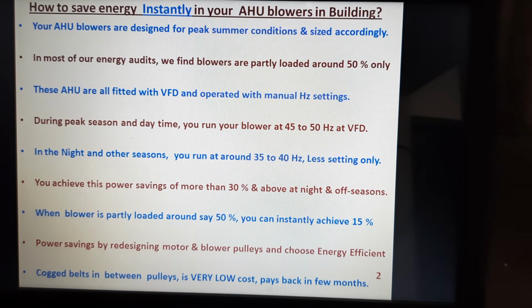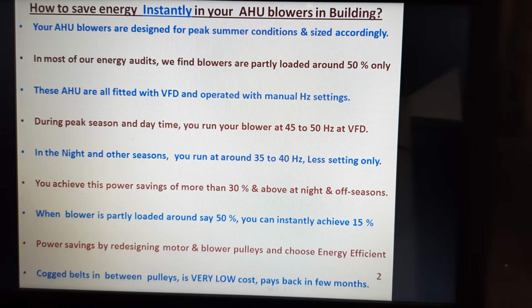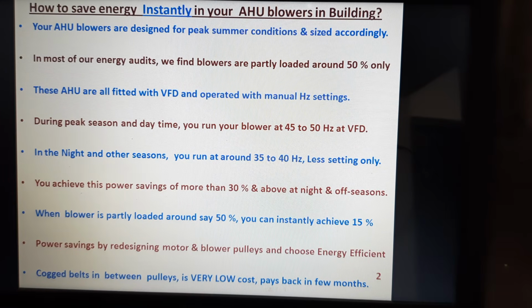Your AHU blowers are basically designed for peak summer conditions and sized accordingly. In most of the energy audits we have conducted in buildings and industries, we find the blowers are partly loaded, around 50% only, especially the air handling blowers. These AHUs are fitted with VFD and operated with manual hertz settings in some of the IT and commercial buildings, and many of the IT buildings have already switched over to BMS. They have incorporated all the HVAC systems in the BMS software.